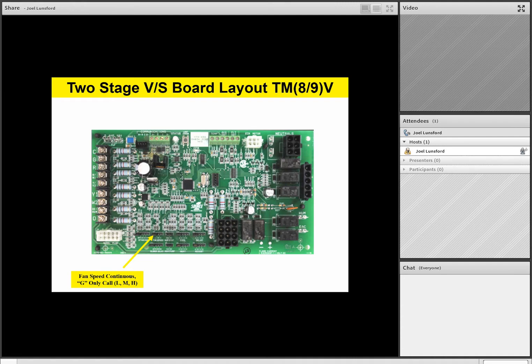Below that, we have our blower delay, and again, that's our heating off delay. So the blower delay is different than our fan speed. Remember, the previous jumper we talked about is fan speed, which is how fast the fan runs continuously. The blower delay is your heating off delay. And again, this tells us how long the fan is going to run after the call for heat is over.